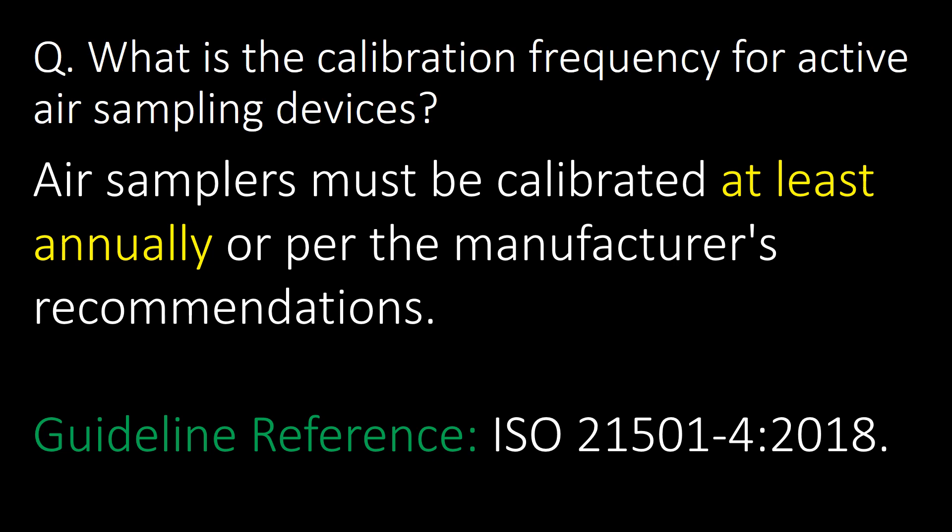What is the calibration frequency for active air sampling devices? Air samplers must be calibrated at least annually or as per the manufacturer's recommendations. Guideline reference: ISO 21501.